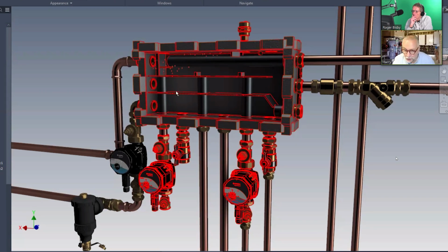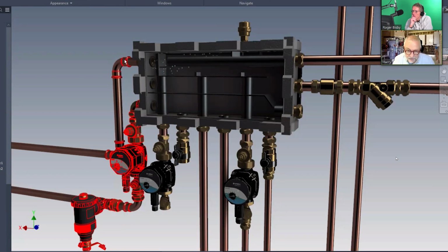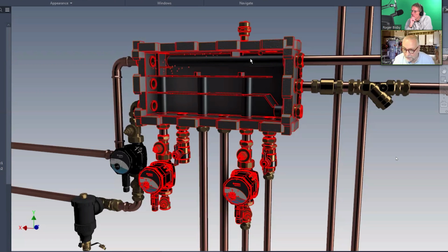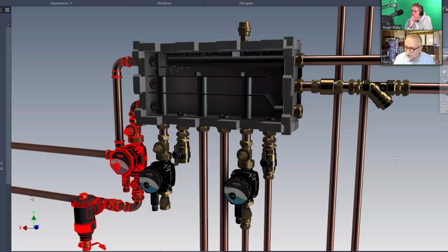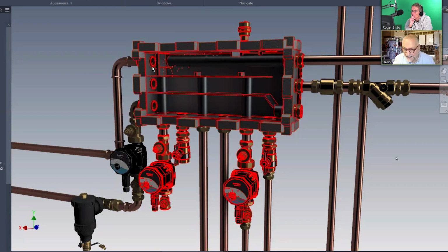If I then put in 2 plates and a large gap on the right-hand side, and a heat pump comes in from this side, it simply flows across the top of the plate, down over the gap, down to the bottom, and back to the heat pump. The heat pump's job is now finished. It has nothing else to do. But when it comes in, if there's any air in the system, because the distance from here to the vent is more than 7 times the diameter of the pipe, because this top flow chamber is the equivalent of a 2.5-inch iron pipe, the water slows down as it travels, and any air gets trapped here and is immediately released.